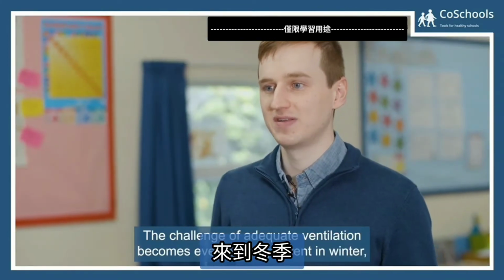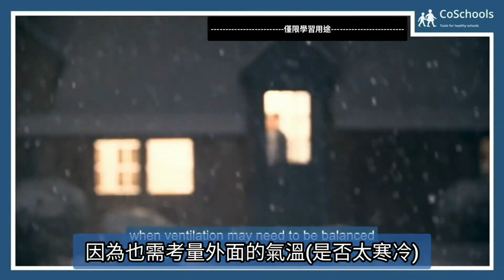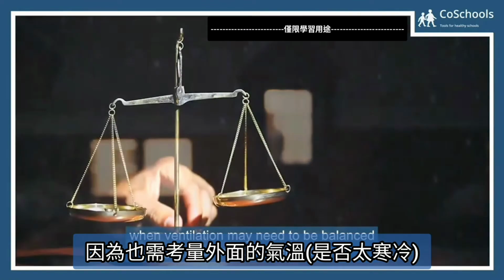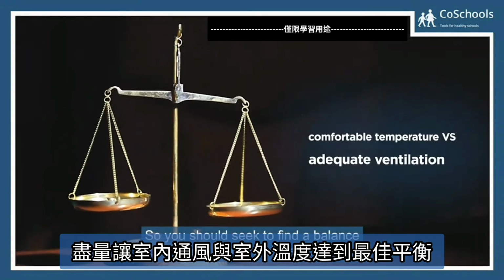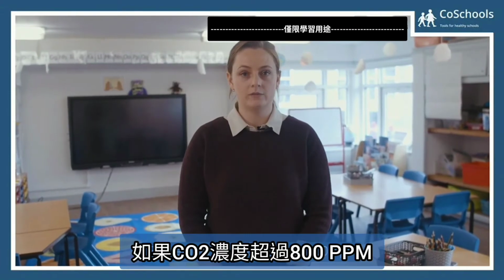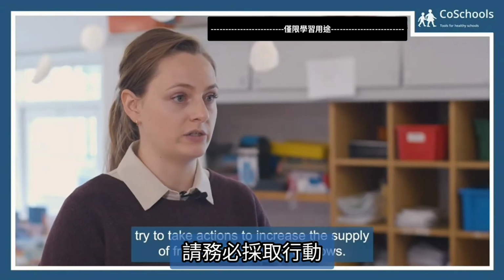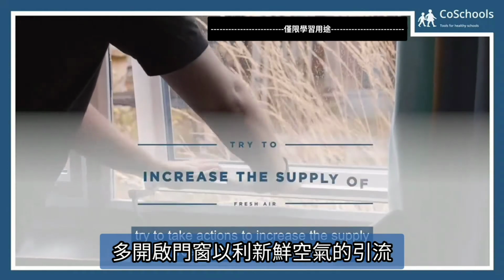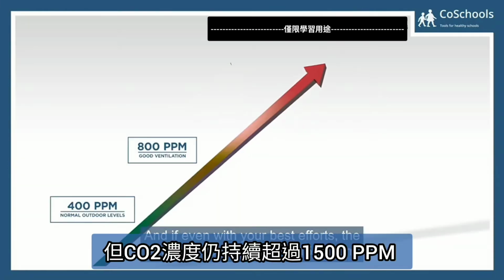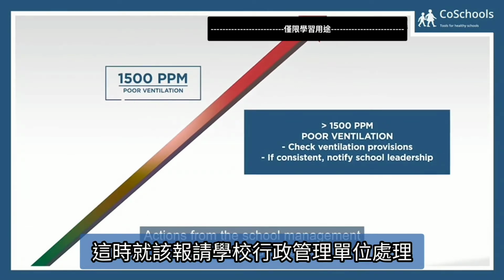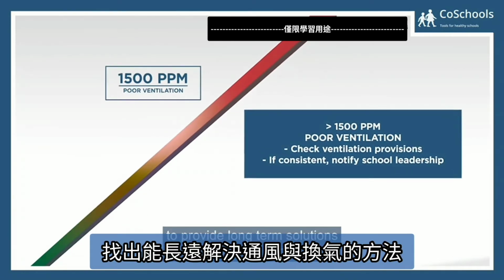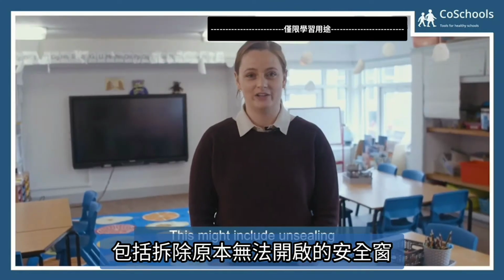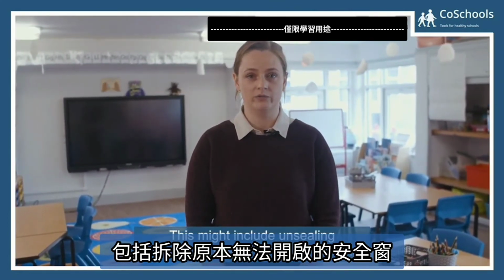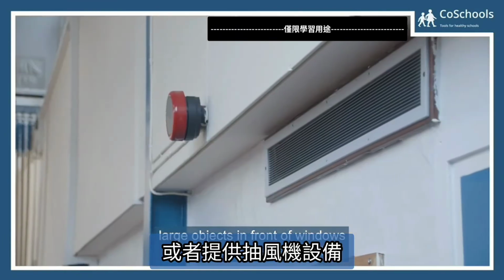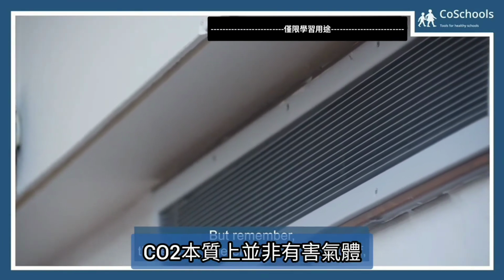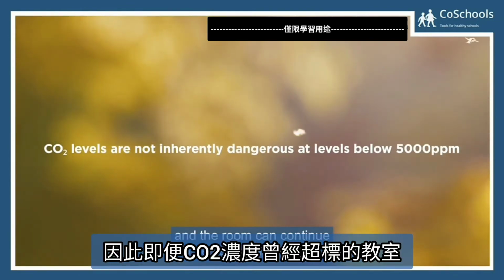The challenge of adequate ventilation becomes even more apparent in winter, when ventilation may need to be balanced against a comfortable temperature. So you should seek to find a balance between a comfortable temperature and adequate ventilation. Remember, at levels above 800 ppm, try to take actions to increase the supply of fresh air by opening windows, and if, even with your best efforts, the levels are regularly above 1500 ppm, actions from the school management teams should be taken to provide long-term solutions to improve the ventilation. This might include unsealing permanently sealed windows, removing large objects in front of windows, or providing passive air grills. But remember, there is no inherent risk from CO2 itself, and the room can continue to be used if appropriate.